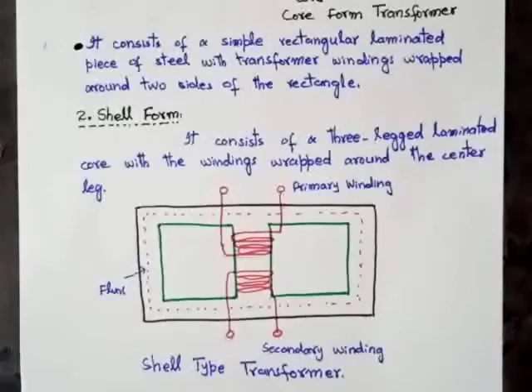This type of core or transformer is called the shell form. As you can see in this figure, there are three legs. This is leg number 1, leg number 2 and leg number 3. Laminated core with the windings wrapped around the center leg. If the windings are wrapped around the center leg, then this type of core is called shell form or shell type transformer. We mostly use type 1, that is the core form transformer, in daily life or in modern life.